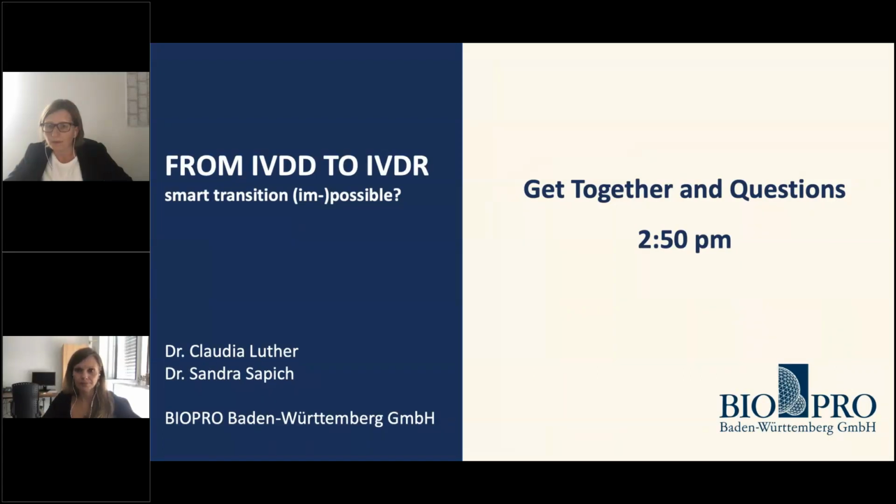So there's more. If an IVD medical device is established for professional use only and this label wants to be removed, is this considered a major change? Who wants to reply? Otherwise I can. I can do as well. So if you're aiming to sell the product now to lay users, then for sure this is a major change because you change the intended use. Because part of the intended use is as well the intended users.